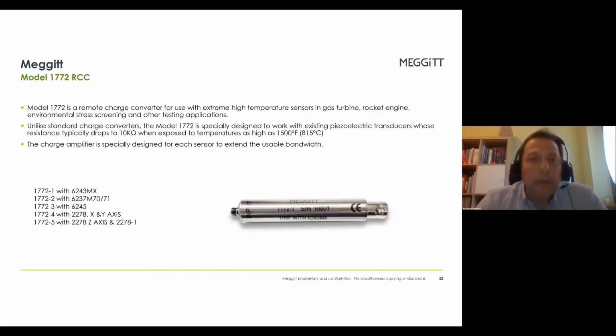It's also capable of using the full temperature range of the sensor, because as temperature increases, the sensor's inner resistance drops. We can go from gigaohms down to kiloohms, even tens of kiloohms. In this case, the unit is capable of managing the lower system impedance.